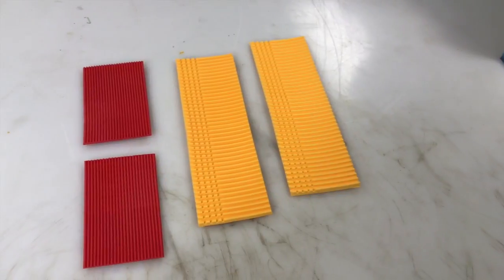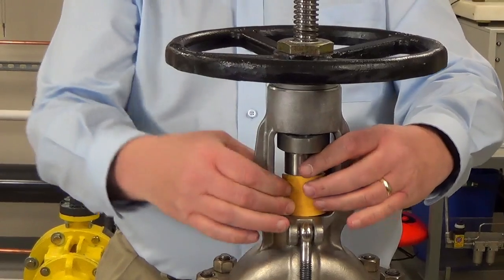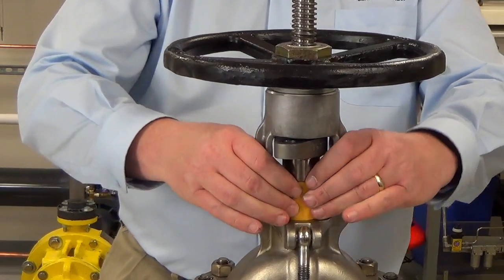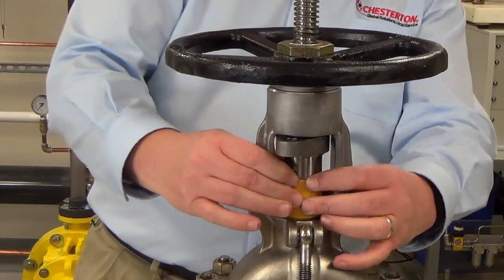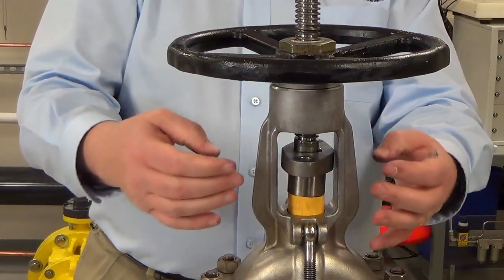A tamping tool is an extruded piece of plastic that has been cut so we can get it around into the stuffing box. You also have to trim the height of this tamping tool so we can get it around into the gland. As you put the tamping tool into the box, make sure that you can bring the gland down and that the ring is fully hitting the bottom of the box. In some cases the tamping tool will be too short and you'll have to add another tamping tool.